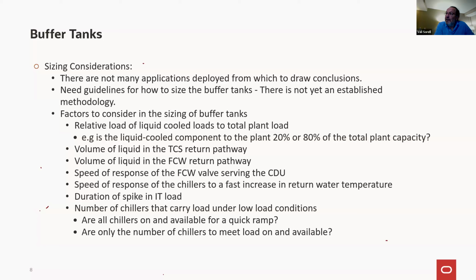That's a great question. Yes, but from the control standpoint, it's harder to get the power monitoring data into a BMS if the BMS is strictly on the mechanical side to be able to get the plant to respond. It's doable if you put your sensing elements just at the outlet of the racks or as close to the racks as you can. You may have a couple of seconds of residence time from when it comes off the chip to come off to the TCS return piping, maybe under 10 seconds. And you may still have a few minutes of additional time as it makes its way to the plant.